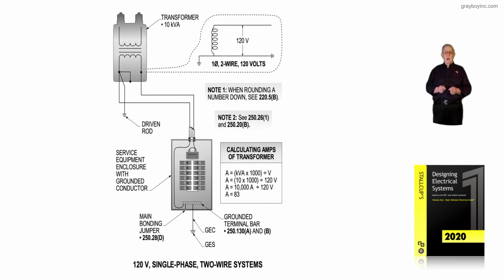And then of course your main bonding jumper, if you, for example, as the designer or installer, were supplementing the screw that grounded the grounded terminal bar to the enclosure, then it would also be sized based upon Table 250.66 in the past. But the 2020 NEC, as you well know, would have a Table 250.102(C)(1) that would be used to size that main bonding jumper. But really, Table 250.102(C)(1) is in there basically as an overlay of Table 250.66.